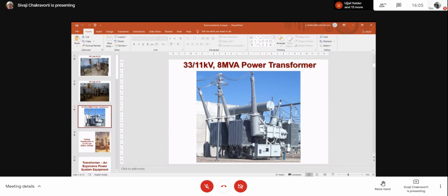You can see here rectangular blocks. You can look at my mouse. What are these? Radiating tank. These are the radiator banks, right? We call it radiator banks. So this is called forced oil cooling. So oil will be pumped from the tank and it will flow through that and go back to the tank. And in the process, it will radiate the heat and cooling will work.